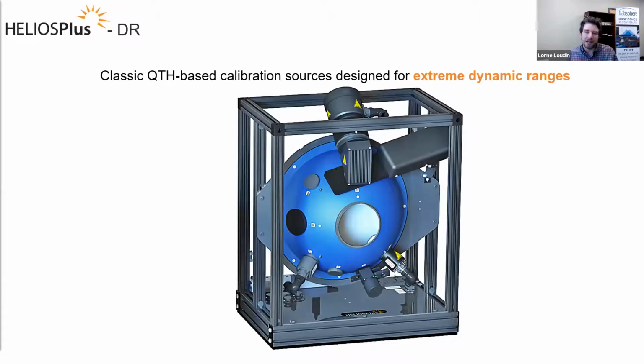So now moving into our dynamic range systems, known as our DR systems. Our DR systems are designed for whether you are testing simple CMOS sensors or multiple gain stage focal plane arrays. You'll find that the maximum flexibility in the D family system and component options are ideal. The Helios Plus DR D family systems are classic QTH-based calibration sources that are designed for extreme dynamic ranges. There are multiple lamps and attenuators and detector choices on the system that allow you to move effortlessly from sunlight to night vision levels.